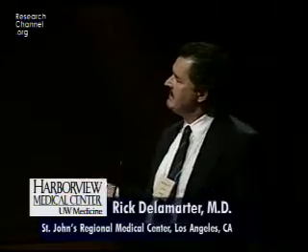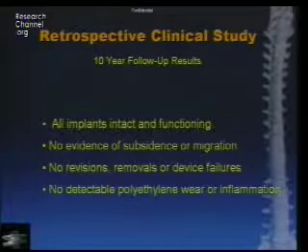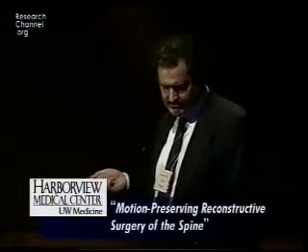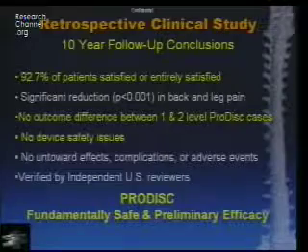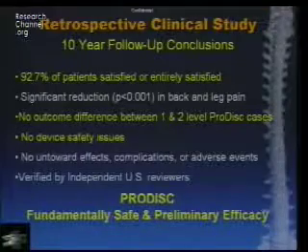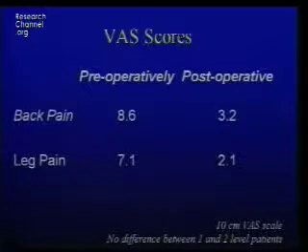Of those 58 patients, 30 had one-level, 21 had two-level, and 4 had three-level treatment. Average follow-up was 10 years. At 10 years, all implants were intact and functioning with no evidence of subsidence or migration, no revisions, removals, or device failures, and no detectable polyethylene wear. This data was taken to the FDA and is what allowed them to okay and begin the IDE study. Basically 92.7% of patients were satisfied or entirely satisfied, proving fundamental safety and preliminary efficacy.